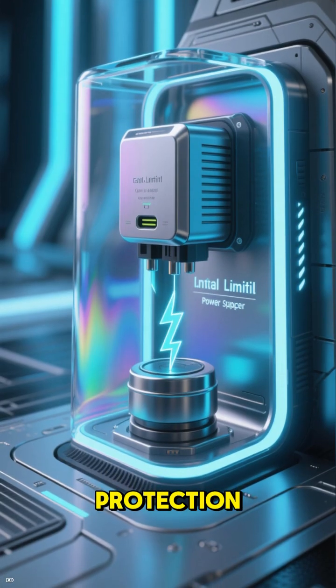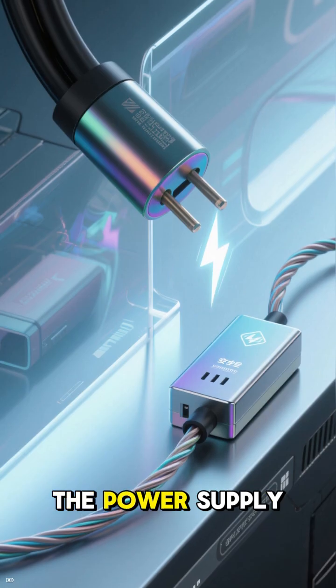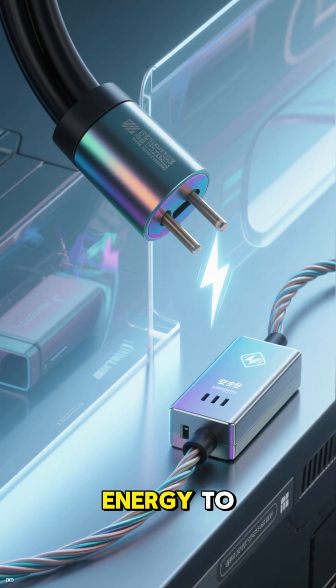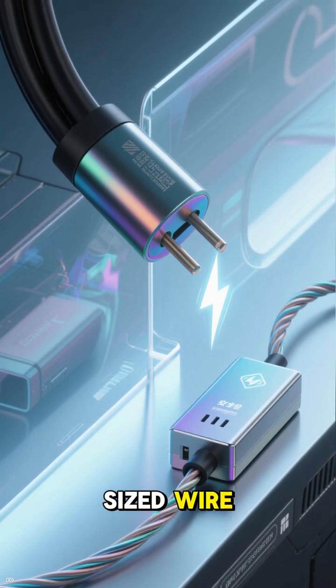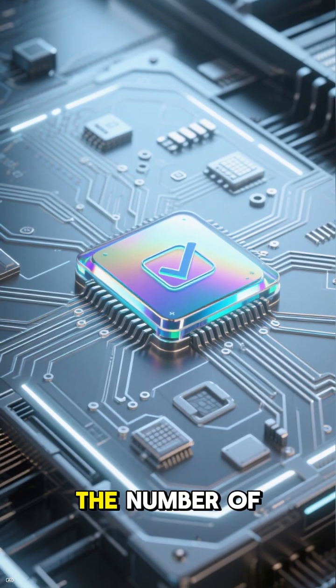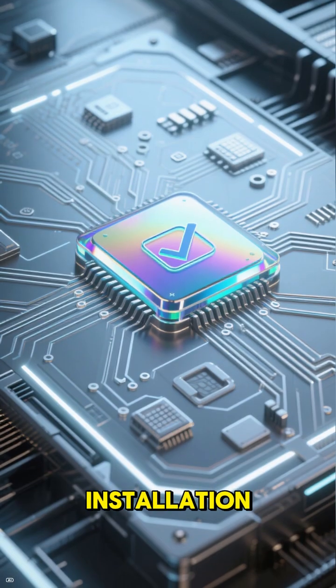Remember how we said the power source itself is inherently limited. That built-in limitation serves as the protection for the entire circuit. The power supply simply cannot deliver enough energy to damage the correctly sized wire. This simplifies the design and reduces the number of components needed for a safe installation.